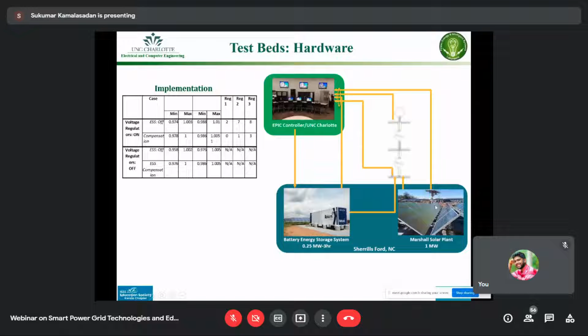So what are the use cases we are working on? One is managing the power grid to reduce the total losses. This is done through an architecture called distributed optimization. Here is a power grid example, with renewable energy connected at different points on the grid, and the goal is to manage these DERs and support the power such that the total losses on the power distribution system are minimized using an algorithm.